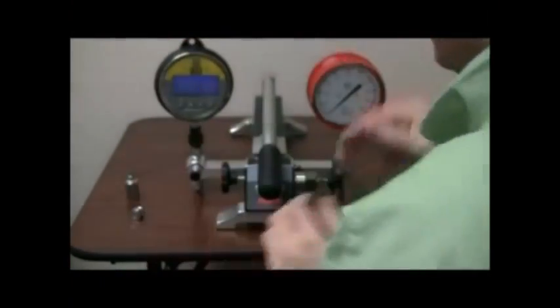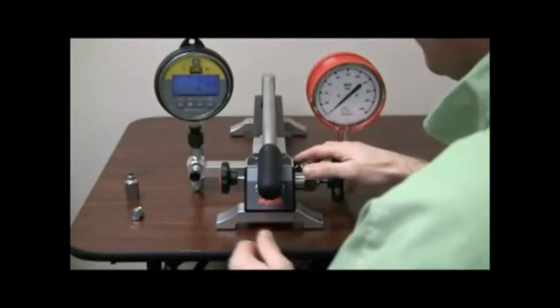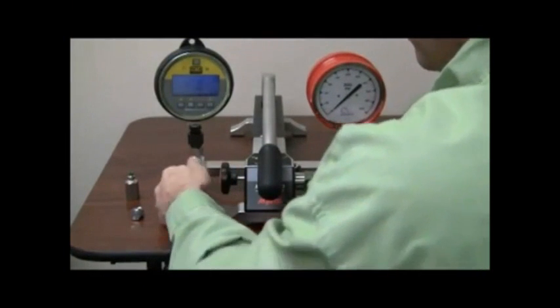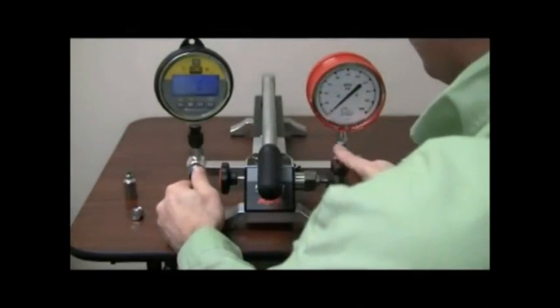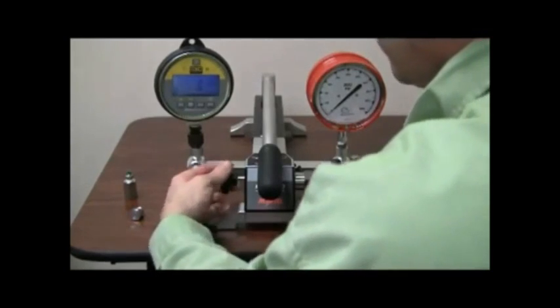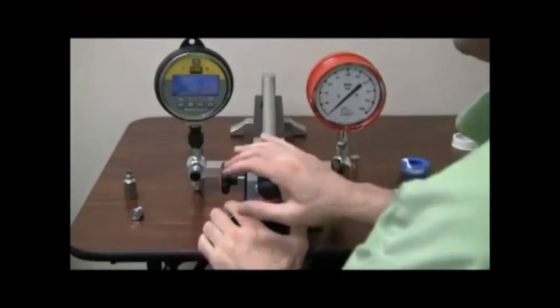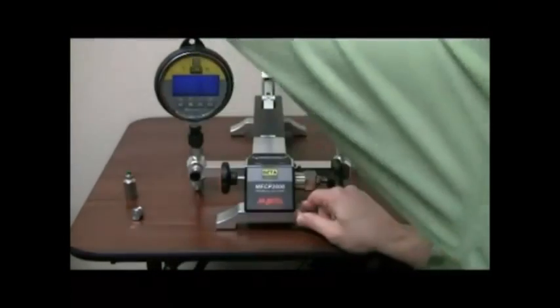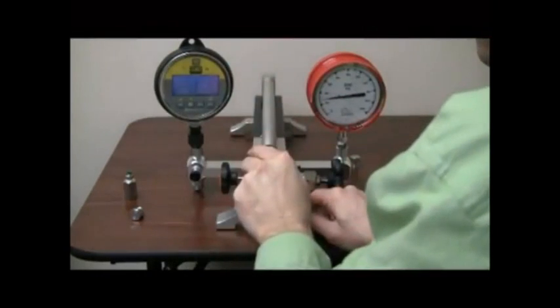Make sure that the pressure switch is switched down when you're applying pressure. Tighten the bleed valve and release valve. Adjust the variator halfway. The isolation valve should be about a turn out for optimum performance.